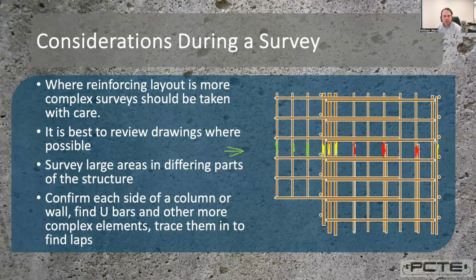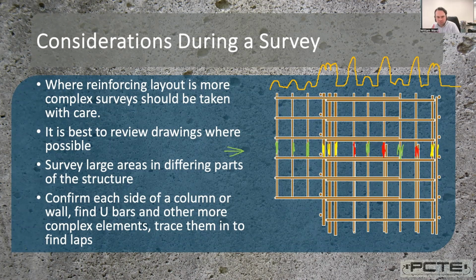And back to a moderate increase there and a more modest value here. And now we need to think about what that means. If we have no reason to believe that the reinforcing cover depths have substantially changed, we should only see a modest change in the signal intensity. So if we were using the operation mode of a line scan, this chart I'm drawing represents signal intensity. It would end up looking something like this, where we have more intense signals in our lapped region, and then weaker signals in the single bars, and there will be a medium intensity signal where bars are close together.